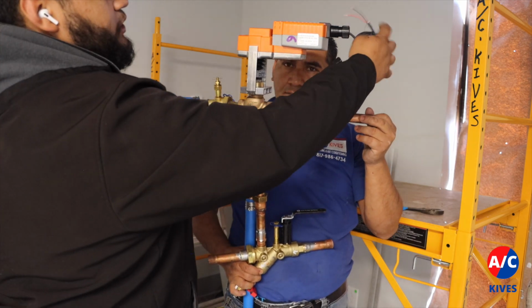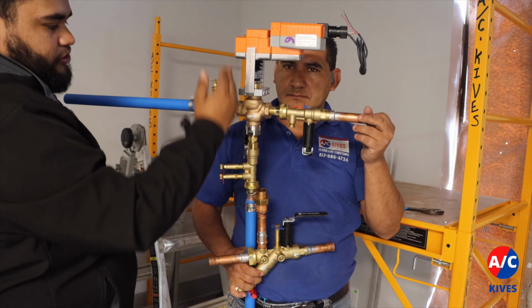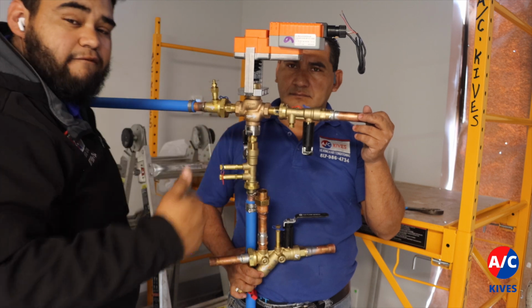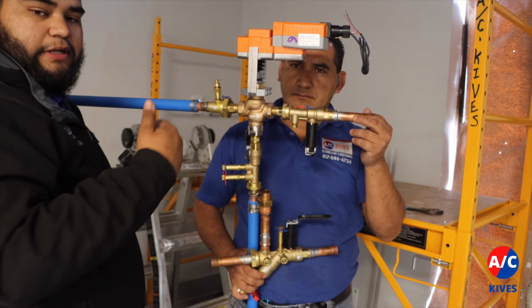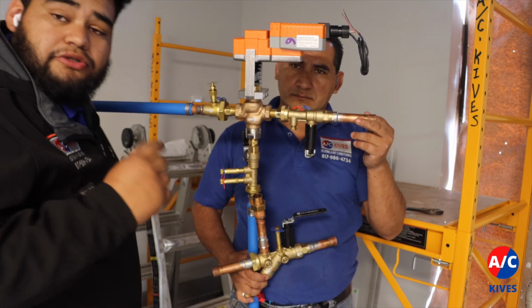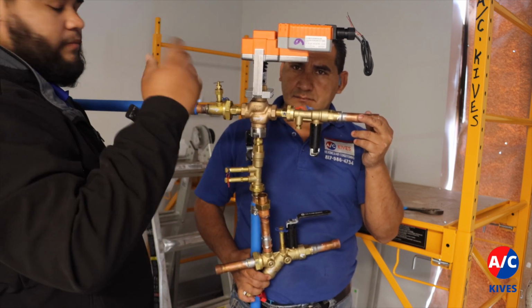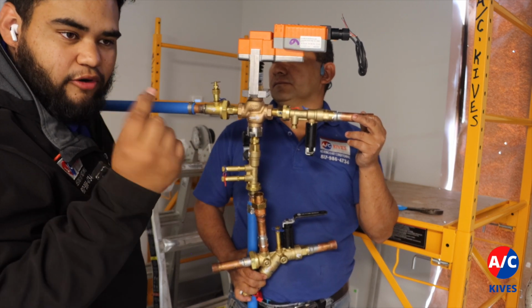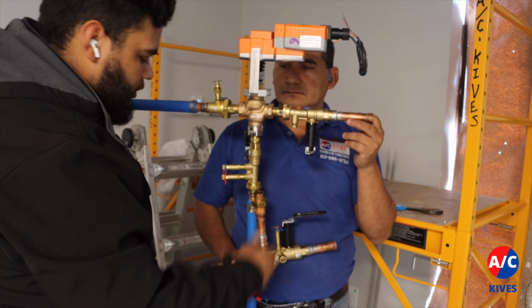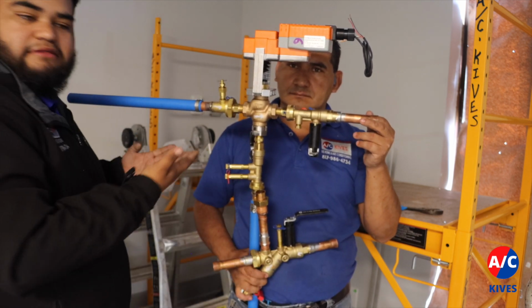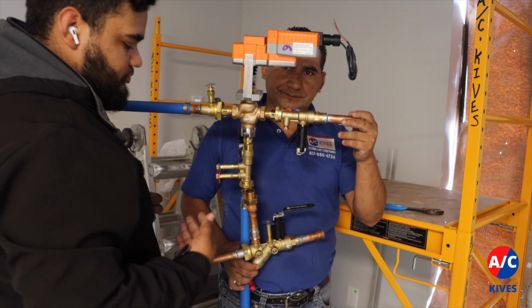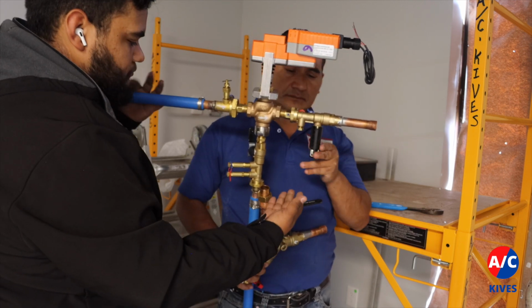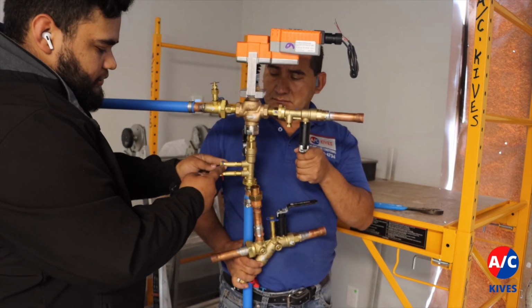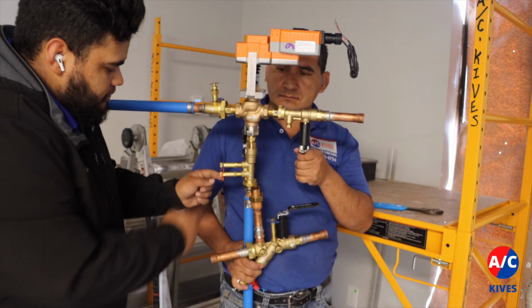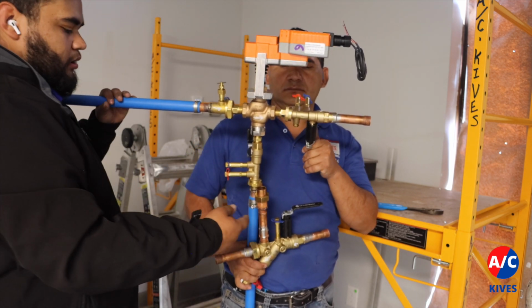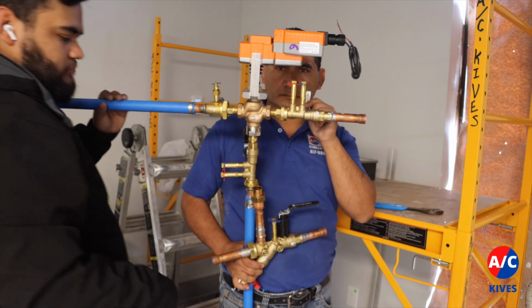It has 24 volts to actually move the actuator up and down, and a 10 volt DC to determine how open it is. I'll show you later in the video how it actually looks when it's opening and when it's closing, but that's pretty much it on how these work - there's nothing too much to it. And then, like I said, these blue ones are for temperatures, these red ones are for pressure, and that's really much to it.